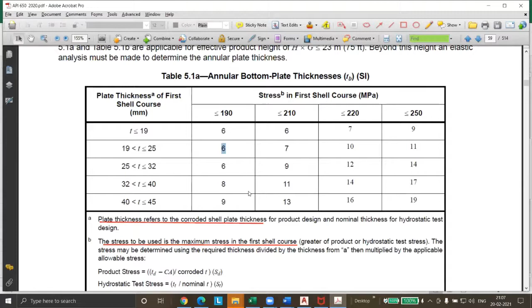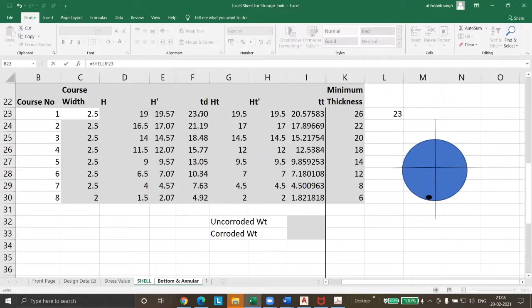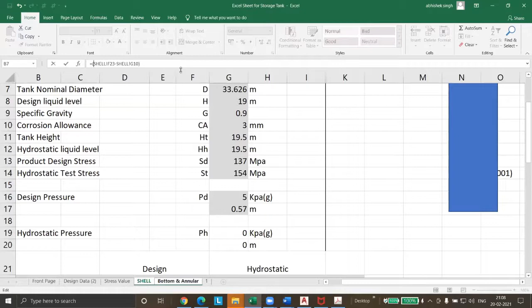So for our case, we can calculate the thickness as per this. Before that, we will calculate the product stress. For product stress, what will we have? T design, so we'll go here, T design minus corrosion allowance, divided by this corroded thickness, or we can have this minus corrosion allowance. Multiply this ratio with SD. We can use SD from here, or on the next page we also have this SD value. So this is 124 MPa.